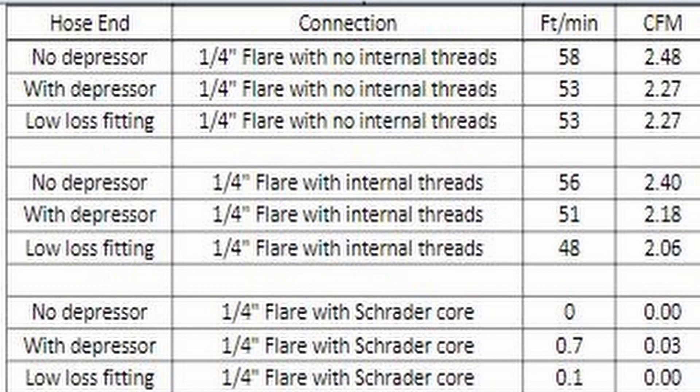Looking at this section down here, we have no depressor with a quarter-inch flare with Schrader core, which means you're pulling zero feet per minute — zero CFM. The next step was without the depressor, basically using a Schrader in there with nothing controlling the opening and shutting force. And as you can see at the very bottom, a low loss fitting with a quarter-inch flare with the Schrader core has the capability of pulling 0.1 feet per minute.